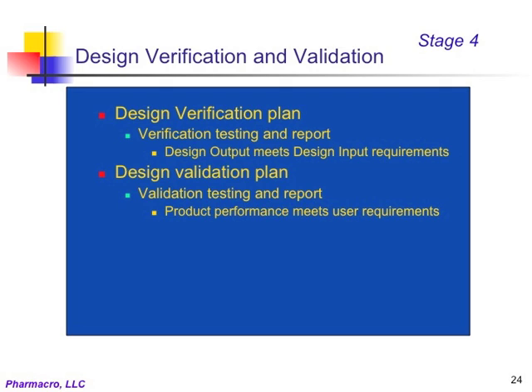Successful completion of design verification is followed by design validation, which involves testing of the device in actual use environment, such as a test lab or clinic or hospital. This is called design validation, and like design verification, it involves a detailed plan with specifics of the testing and the criteria for success. Testing involving human subjects may require approval from the FDA prior to initiation of testing, and this is called Investigational Device Exemption or IDE. Through the IDE process, the FDA ensures that testing of a non-approved device on human subjects does not expose the subjects to safety risks.